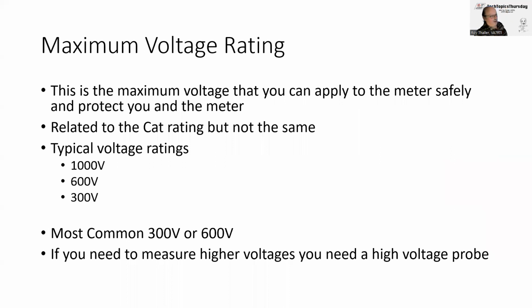So the next thing you need to look at after the CAT rating is your meter's voltage rating. And I'll show you some examples. It could be a 1,000 volt rating, a 600 volt rating, or a 300 volt rating. Most meters will be either 300 volts or 600 volts. If you need to measure higher voltages, you need to get a high voltage probe that goes with your meter.